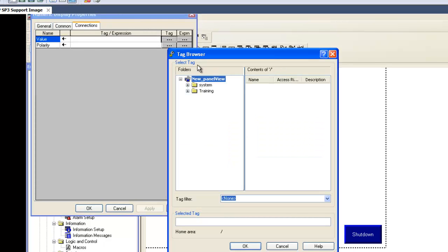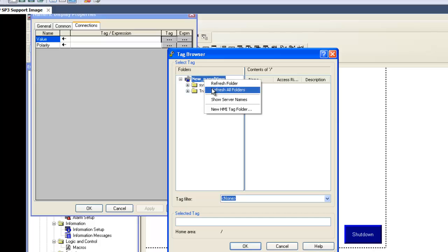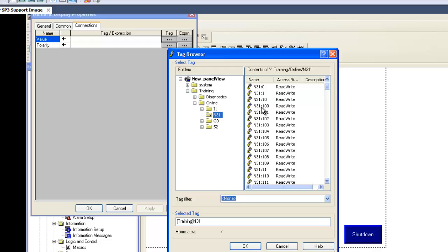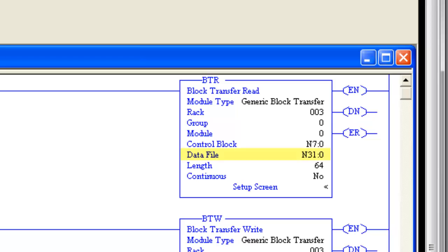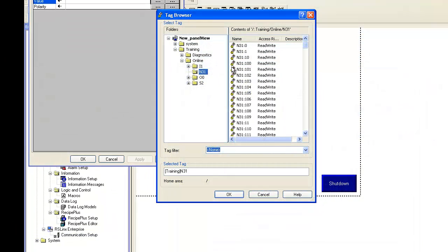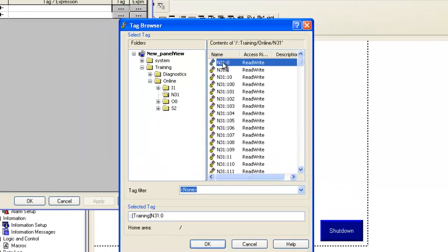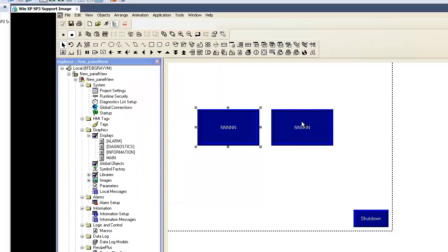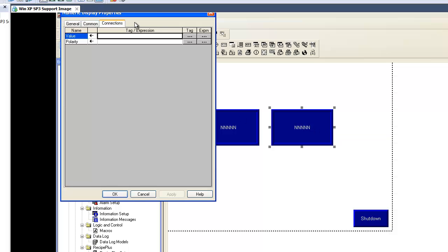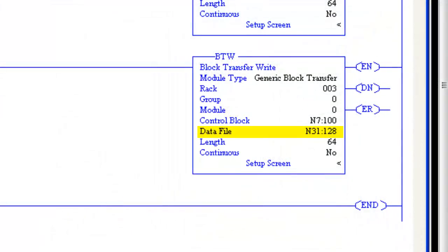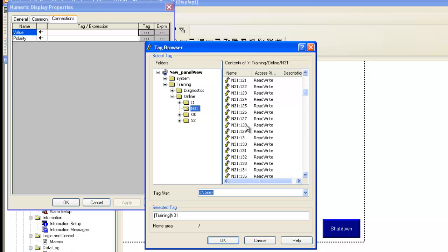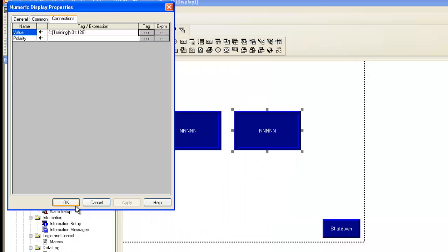Now we can scan tags in the existing PLC. Right-click on the first display and choose Properties. Under the Connections tab, click under the Tags cell. Right-click on the project and choose Refresh All Folders. Expand Training and Online, and you can see the N files in the PLC. Looking at the PLC BTR, the first data file is N31:0. Back in FactoryTalk we'll choose N31:0 and select OK. For the second display we choose the first file for the block transfer write, which is N31:128. Select OK.